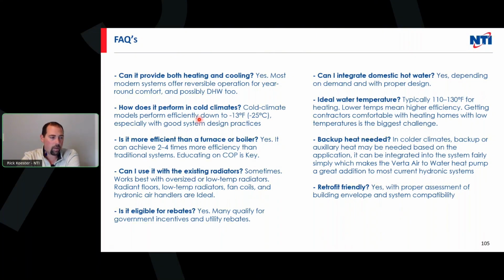I'd love having some kind of a backup, so having a gas boiler as well as the indirect, where we're not doing 100% of the load on either machine, is going to save the most energy for that home. And we also have, God forbid something happened to one, we always have a backup there. So we do perform well in cold climates. Understanding how to design a system properly is going to be the most important part there. It is more efficient. We talked about COP.